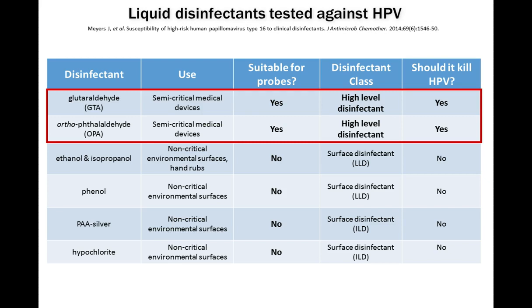So here is a table of the different disinfectants we used. You can see on the left the different disinfectants: glutaraldehyde, OPA, ethanol, isopropanol, phenols, peracetic acid, and hypochlorite or bleach. We list here their use, whether they're typically used for semi-critical medical devices, or non-critical environmental surfaces or hand rubs. According to definition, are these suitable for probes? The top two, the glutaraldehyde and the OPA, are defined as suitable for probes. They both, the GTA and OPA, are in the class of high-level disinfectants. And according to definition, as we just went over, they should be able to kill HPV.